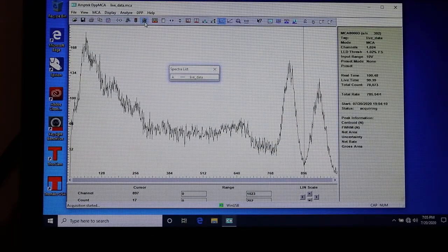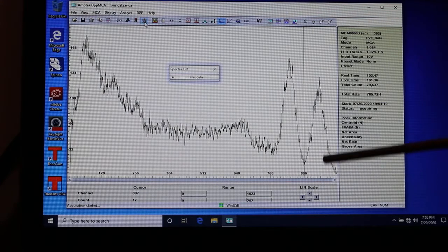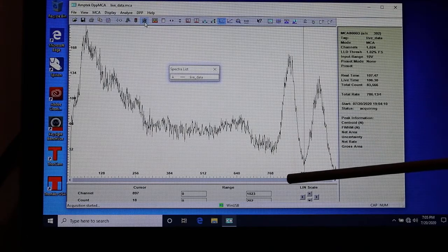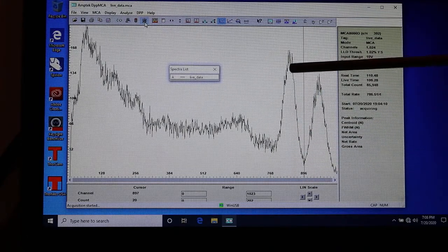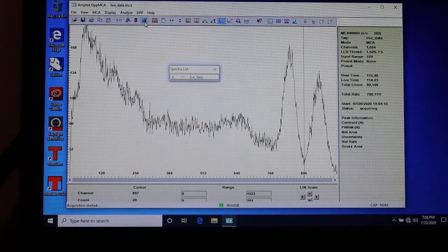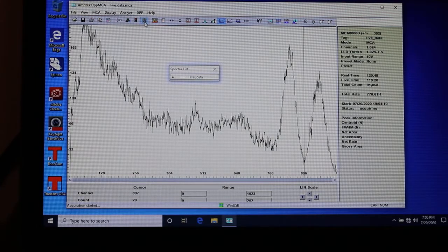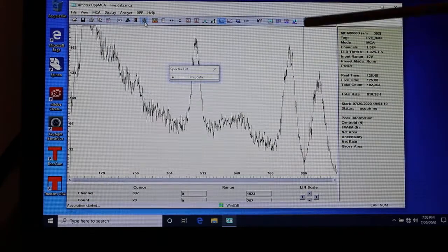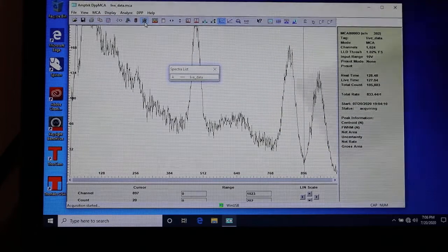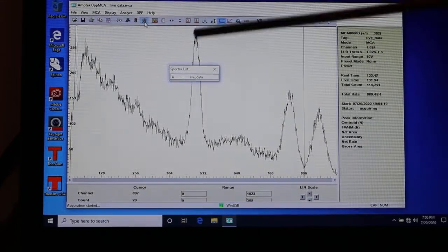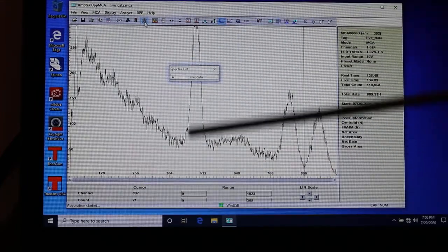At the moment, the way it's running, it looks like channel about 950 corresponds to 1.3 MeV. Over here, channel about 775 or so corresponds to 1.1 MeV. Let me take the cobalt-60 off and put the cesium-137 back on. Here we go. I am not going to turn the amplifier up to move this peak over. I'm going to leave it, because now I have a couple of channel energy correspondences from the cobalt-60, and it looks like channel about 505 or so corresponds to 663 keV.